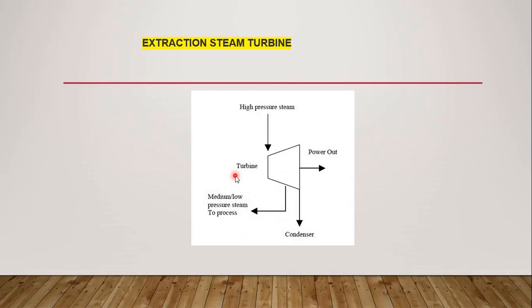The first outlet extracts steam at intermediate pressure for feeding the heating process, while the second outlet extracts the remaining steam at low pressure for condensation. The extraction of steam from the first outlet can be stopped to generate more output — control valves at this outlet make this turbine very flexible and allow adjusting the output as per demand. The steam from the second outlet goes to the condenser chamber where cooling water brings the temperature of the steam down.